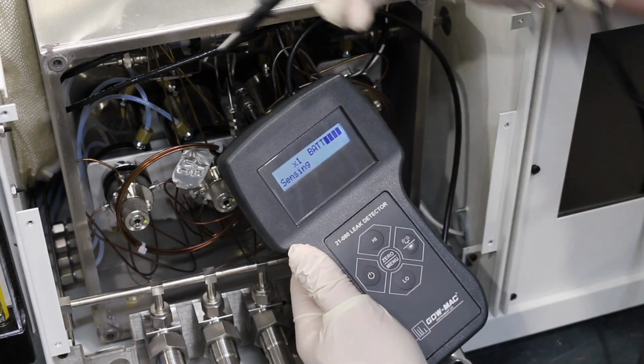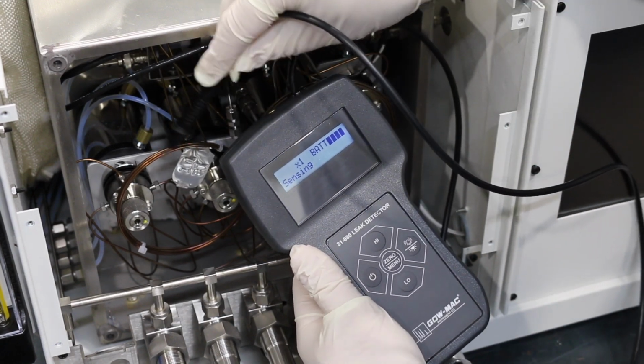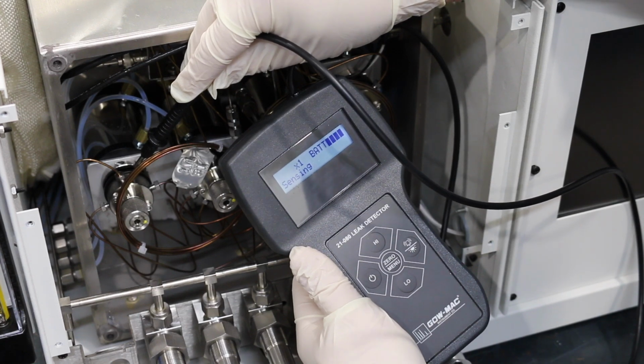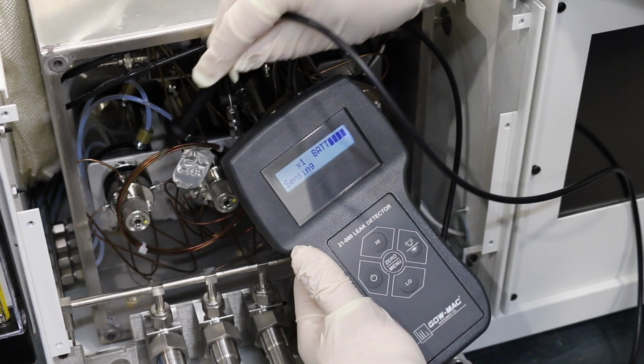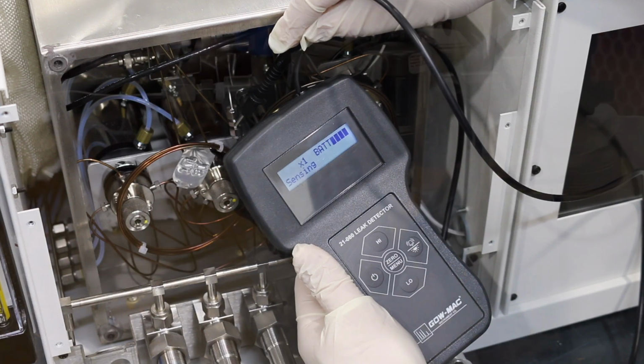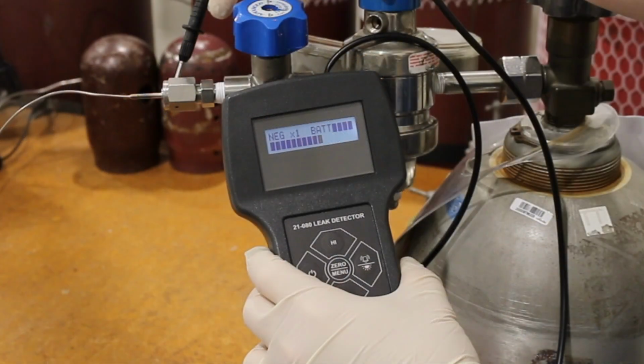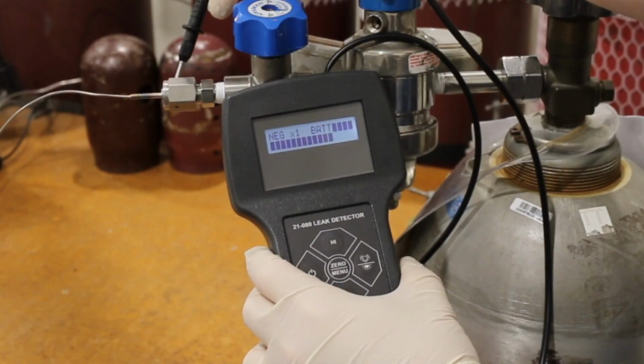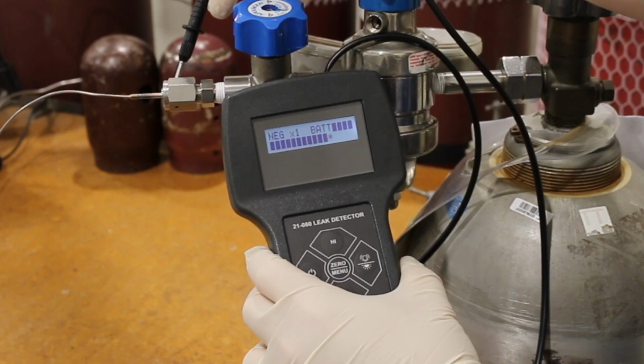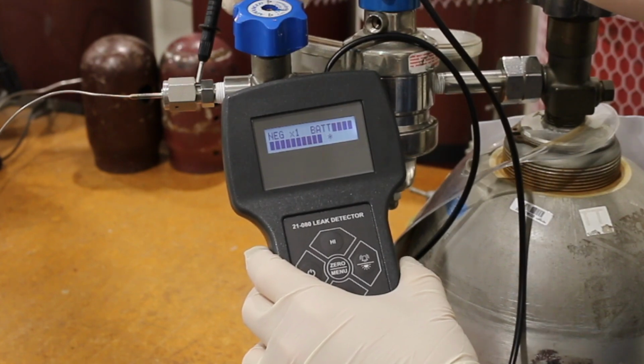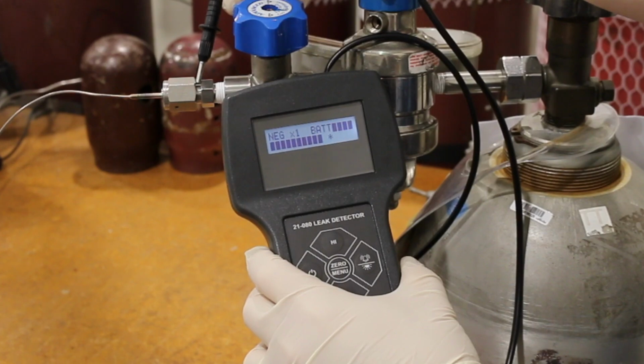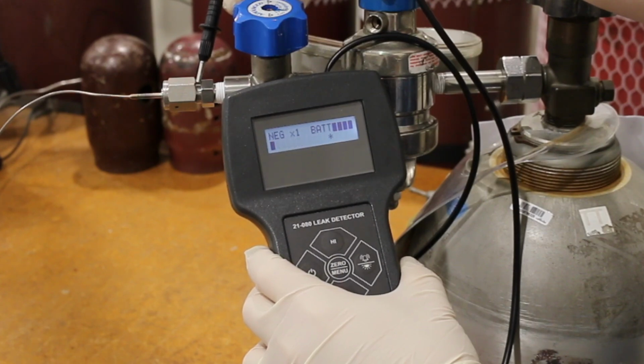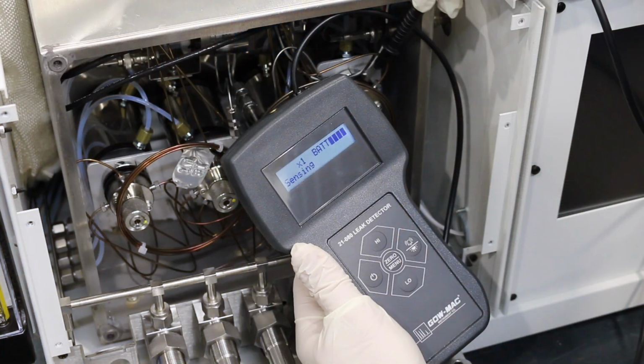6. To start your leak detection after the zeroing process is done, simply place the probe near the target area or fitting. Move the probe around the area you are looking to check. If a leak is detected, segments on the bottom row of the display will appear. The number of segments from 1 to 16 illuminate in proportion to the intensity of the signal. This is proportional to the concentration of the sampled gas.